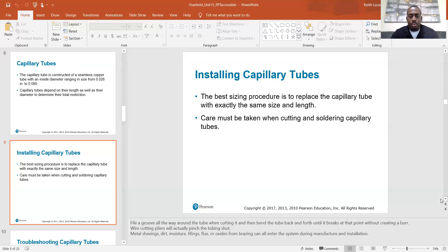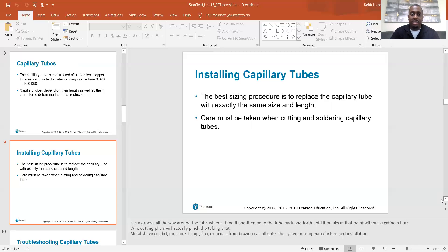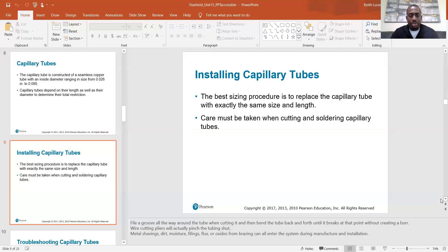Metal shavings, dirt, moisture, filings, flux, or oxides from brazing can all enter the system during manufacture and installation. Take extra care whenever you're brazing copper lines — suction line, discharge line, cap tube, whatever — to avoid getting any debris inside the tubing. All you want inside your system is clean refrigerant. Anything else will give you issues, and the vacuum pump can only do so much, so just take care whenever you open the system.